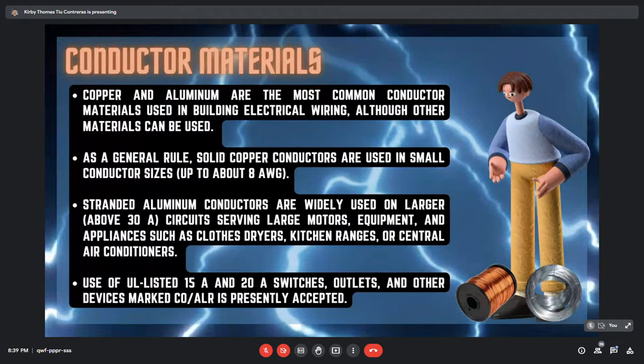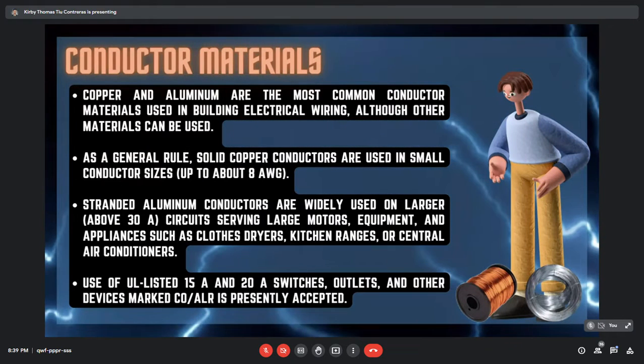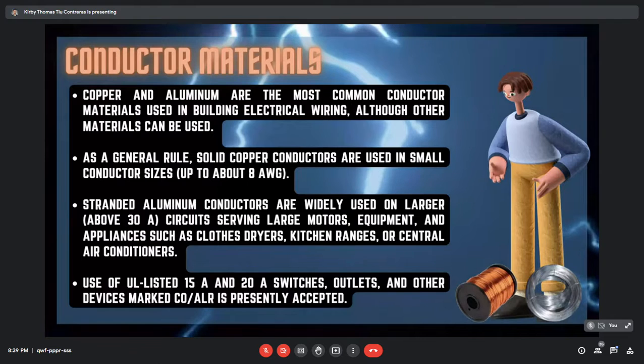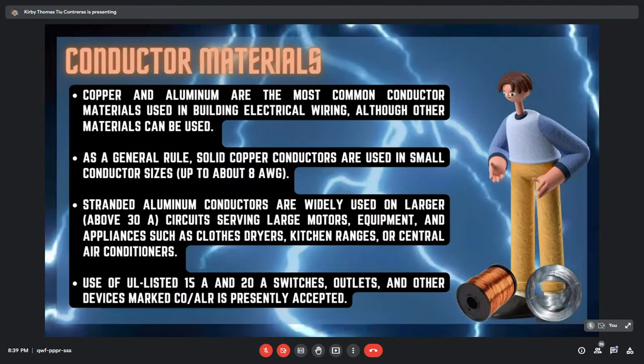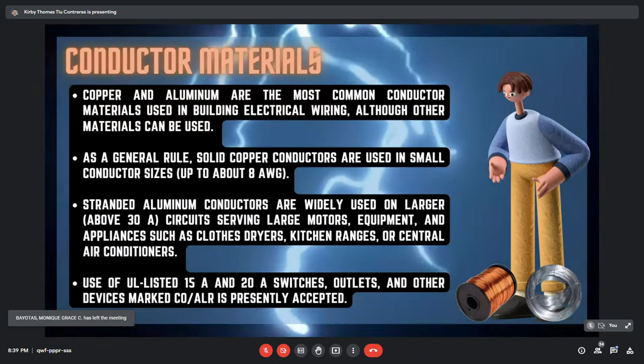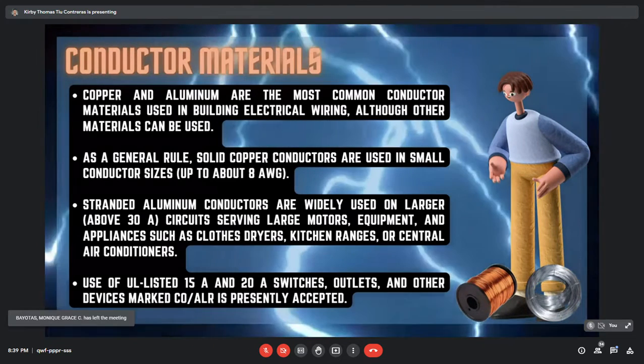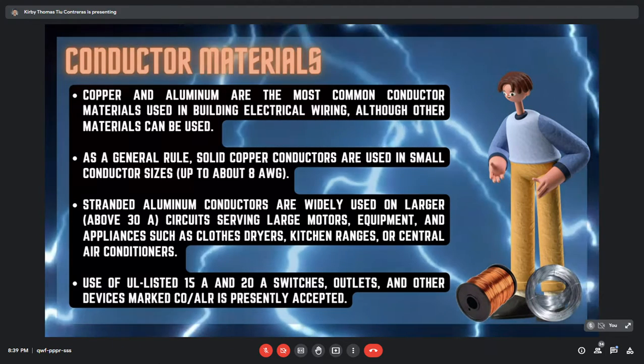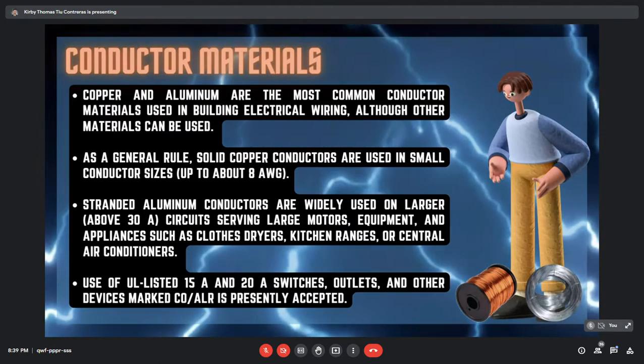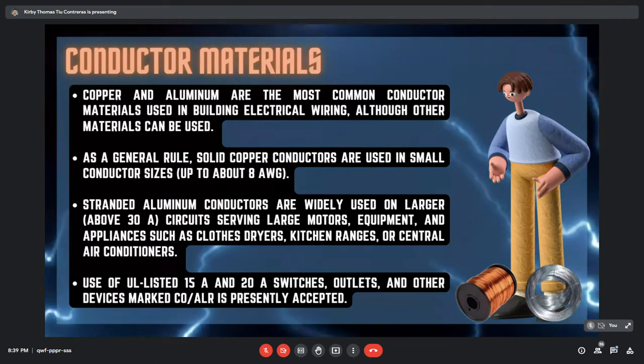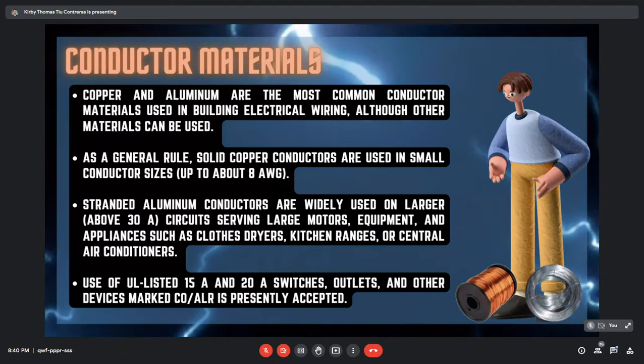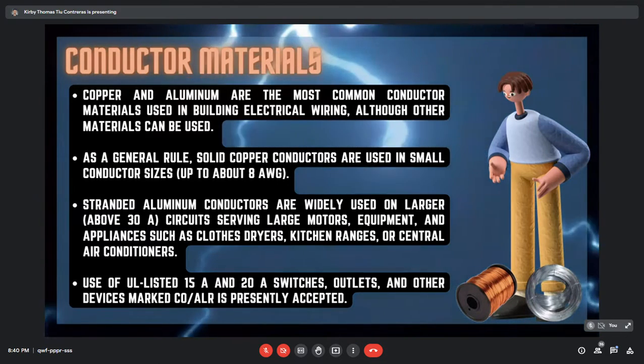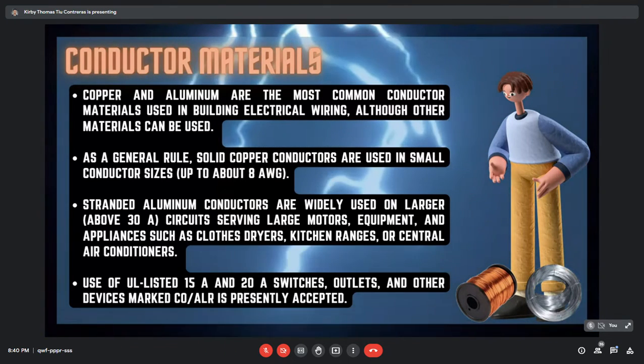So, conductor materials. Copper and aluminum are the most common conductor materials used in building electrical wiring, although other materials can be used. As a general rule, solid copper conductors are used in small conductor sizes, up to about 8 AWG. Stranded aluminum conductors are widely used in larger circuits above 30 amps serving large motors, equipment, and appliances such as clothes dryers, kitchen ranges, or central air conditioners. The use of UL listed 15 amp and 20 amp switches, outlets, and other devices marked CO/ALR is presently accepted. CO/ALR means copper aluminum revised.